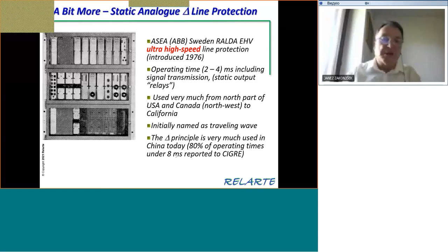But it was not really traveling wave protection because it was looking at changes, delta changes in voltages and currents, for each phase separately on each line. And what is very interesting is that this delta principle has been very much used in China, and is used also today. And Chinese companies reported at a CIGRE meeting, I think it was in Paris 2010, that 80% of operating times with this protection on very high voltage power lines were under 8 milliseconds.